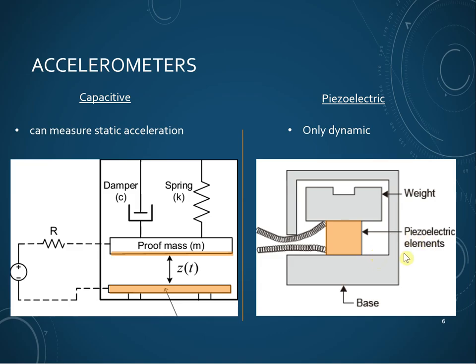The key difference between these two accelerometers is that capacitive accelerometers can measure static acceleration — a very good example of static acceleration is the gravitational pull of the earth — whereas piezoelectric accelerometers cannot. That's really the main difference between the two.